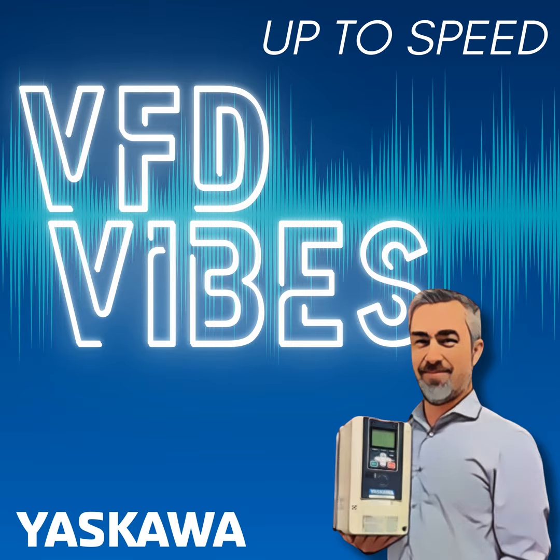And one of the problems if you don't have a grounded system is, first of all, the voltage now across these capacitors is undefined. And secondly, with all that energy coming back from the capacitive leakage of the output, the PWM part of the drive is usually enough to pretty much ruin the capacitors that would be in a typical RFI filter. So RFI filters are generally not a good suggestion if you have an ungrounded system. In fact, if you read the fine print on an RFI filter, it will demand that you are connected to a Y-connected, solidly grounded type system.